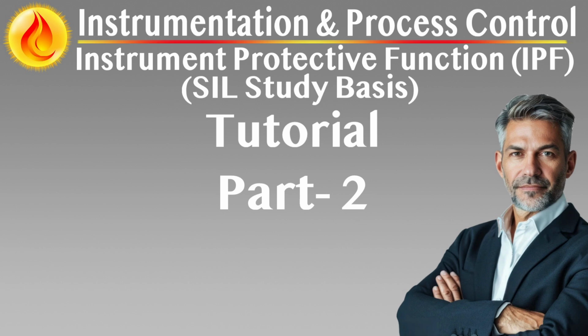Economic risk and SIL allocation. While safety-driven SIL targets often default to conservative levels, economic-driven SIL requirements allow for more nuanced trade-offs. SIL-1 may be sufficient where downtime is tolerable and recovery is straightforward. SIL-2 may be justified where financial exposure exceeds acceptable thresholds or insurance coverage mandates higher reliability. SIL-3 is rarely assigned based on economics alone but may apply to ultra-high-value processes or proprietary assets.